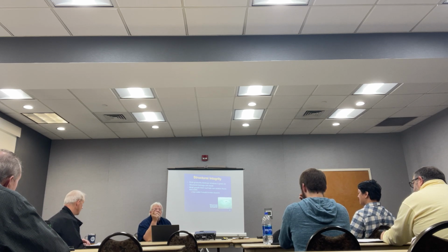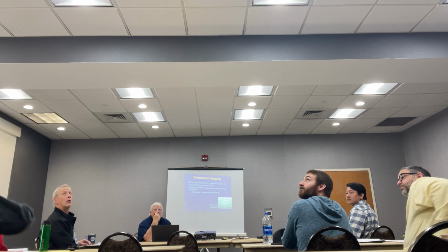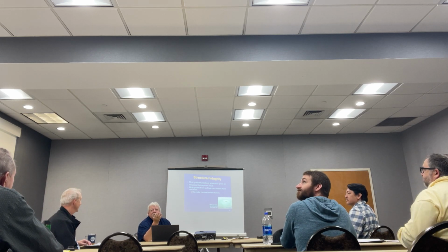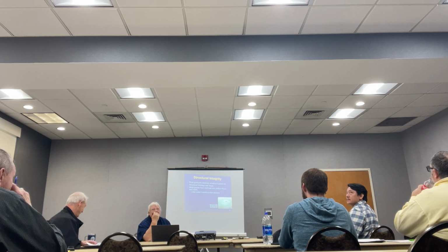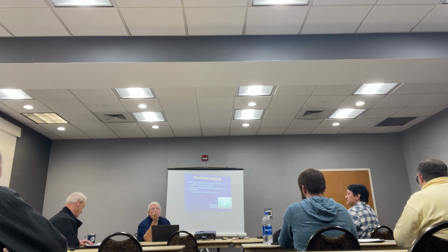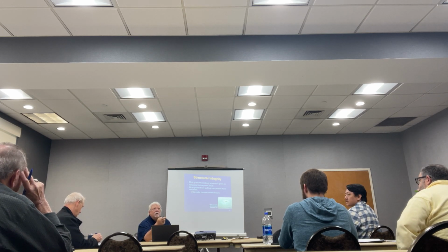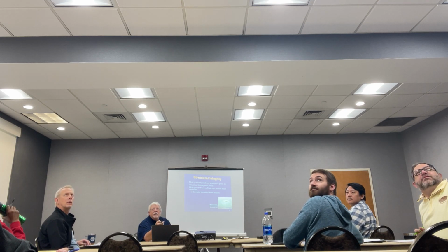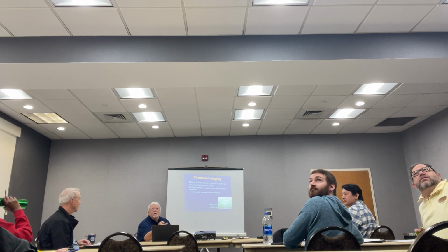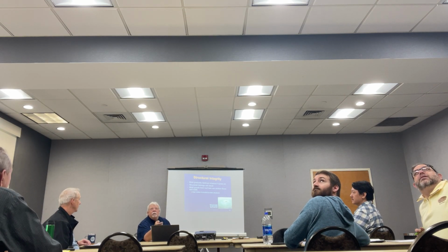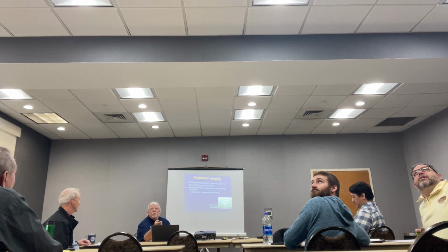And look up there at that vent right there. You see the mold all around it? So you want to try and tell me that there's not mold in this room? But are any of us having symptoms about it? No. And the other thing is, turn around and look right there where that red dot is. That's where condensation builds up, because this one blows out, that one blows out, and this one sucks the air back in. So from here to here, there's a condensation problem.